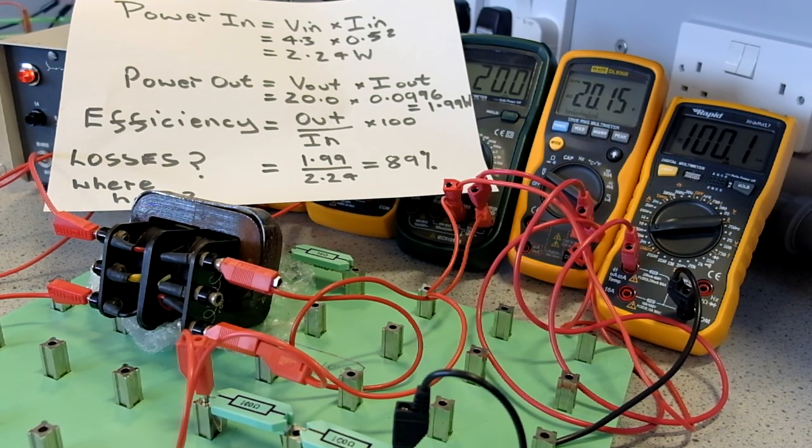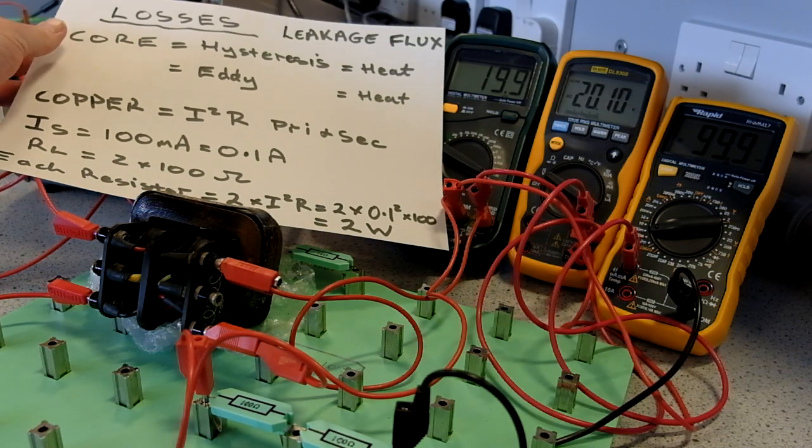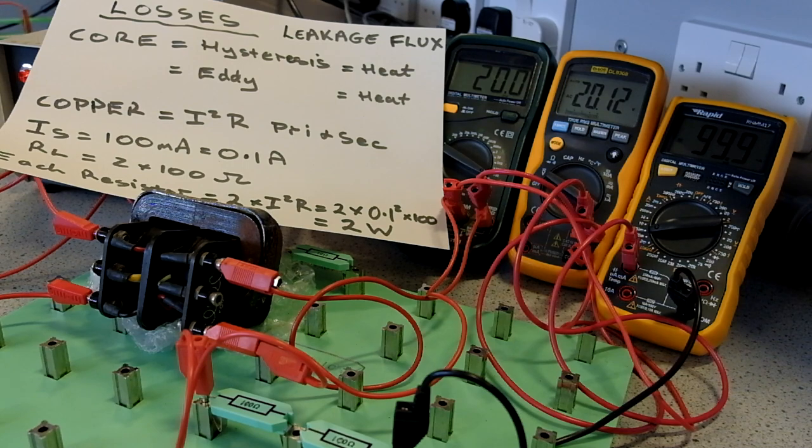So where do those losses come from? As discussed, losses in the system: we have core loss of hysteresis, which is a non-linear effect in the core in terms of magnetizing and demagnetizing, results in heat loss. We have currents induced in the metal core. We can minimize them by laminating the core, but we will have eddy current, so that results in heat loss.